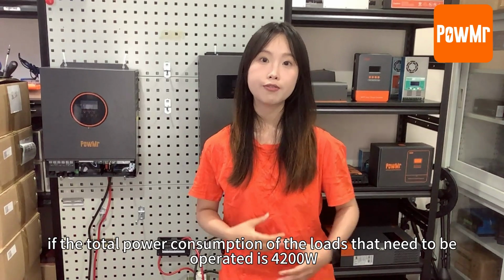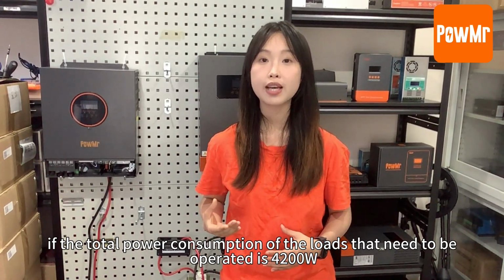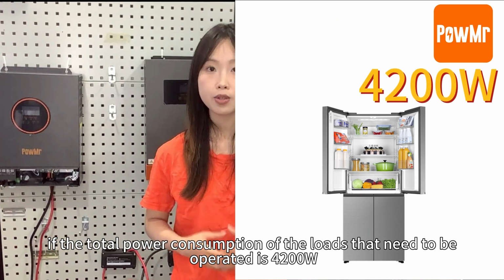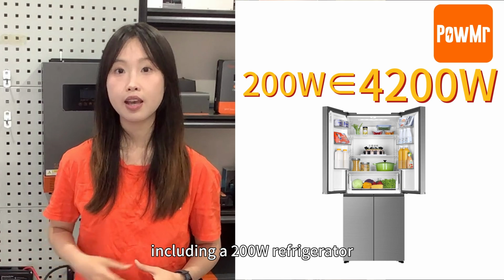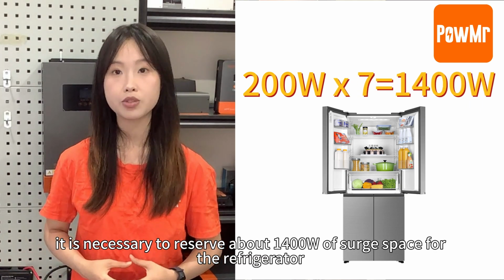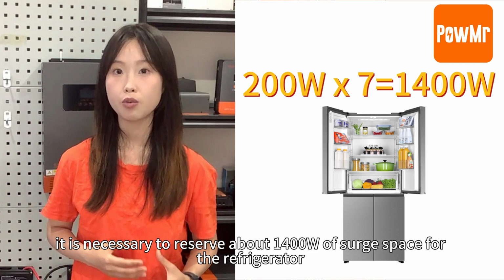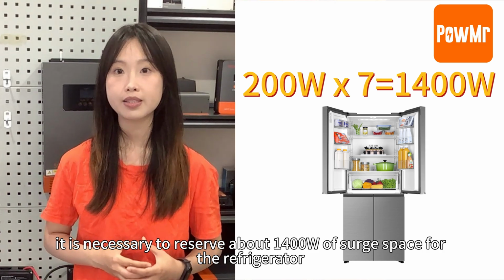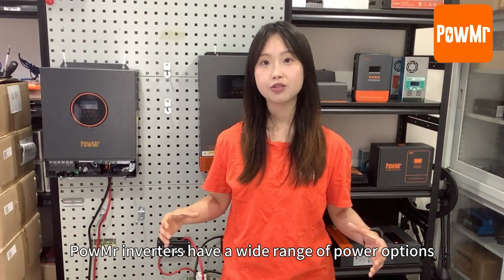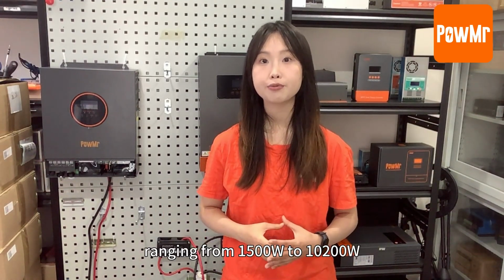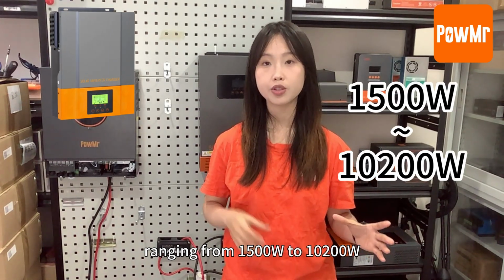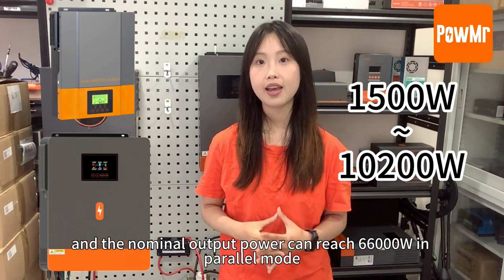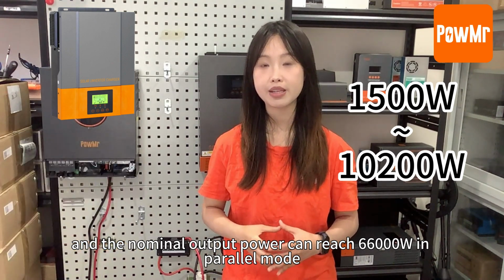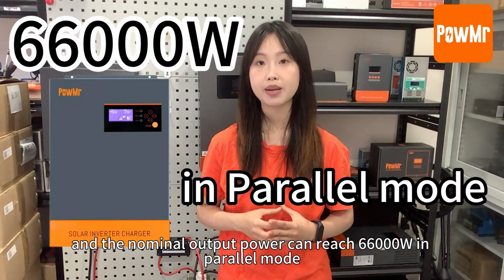For example, if the total power consumption of the load that needs to be operated is 4,200 watts, including a 200-watt refrigerator, it is necessary to reserve about 1,400 watts of extra space for the refrigerator when selecting the inverter. PowMr inverters have a wide range of power options, ranging from 1,500 watts to 10,200 watts, and nominal output power can reach 66,000 watts in parallel mode.